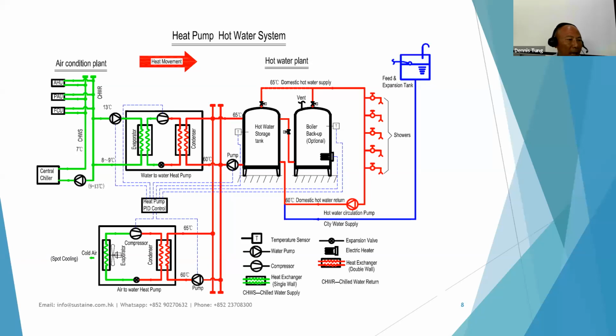An air-to-water heat pump absorbs heat energy from the outdoor ambient and transfers the heat energy into the hot water system. So if we put 1 unit of energy into the air-to-water heat pump, we can have 2 to 3 units of energy going into our hot water system. That is very, very effective and very, very efficient, and it can simply replace the use of a gas boiler or an electric boiler. So, okay, this is the explanation of the heat pump hot water system.